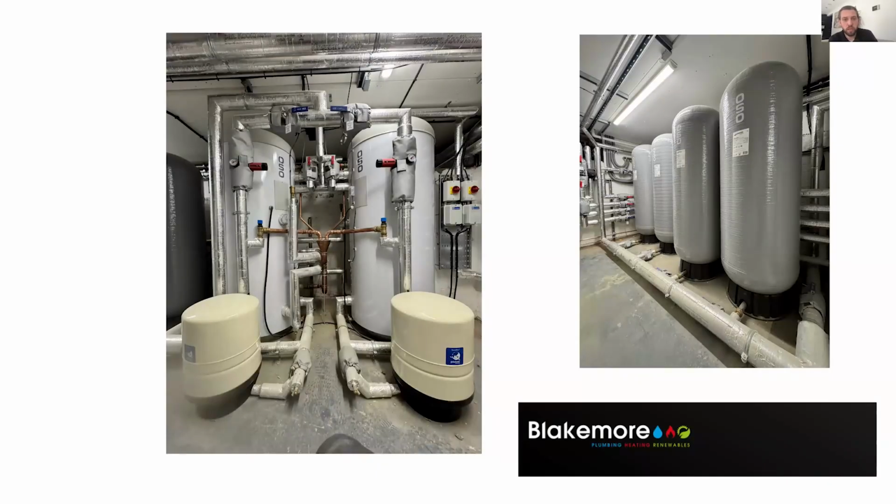So they're the 200 litre cylinders there. Now these are piped off one heat pump each, so each one does its own cylinder. Depending on what we want and when we load shift to these, they run a Legionella cycle once a week if it's not being used. Then we've got motorised WRAS-approved valves at the back that just open and close depending on what cylinder is on. Same with the secondary return, just so it doesn't pull through the other cylinder.